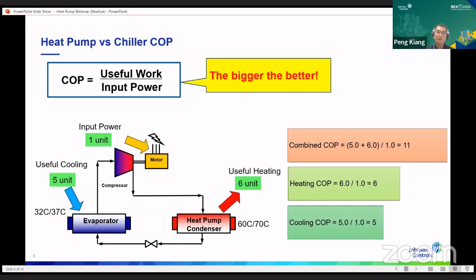Many practicing engineers today look at them separately, which is cooling COP and heating COP. Now, if we combine these two together, and let's say we want to use this heat pump chiller to create cooling and also create heating as another useful form of energy, then you can imagine that these 5 units of energy for cooling and 6 units of energy for heating can be combined with just 1 unit of power. So that combined COP is much, much higher than that individually for cooling or for heating. That is the overarching idea behind how a heat pump is so much more useful and so much more efficient than a boiler.